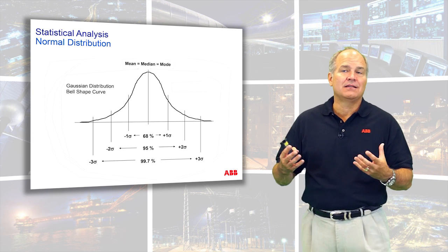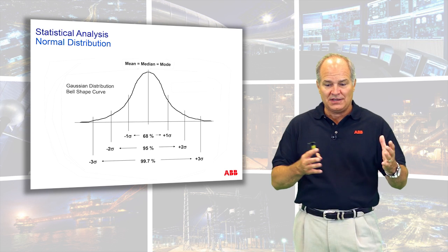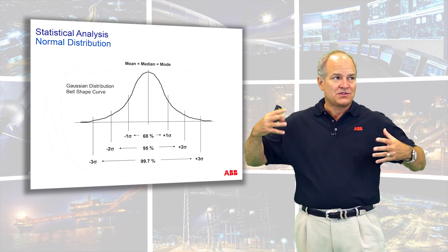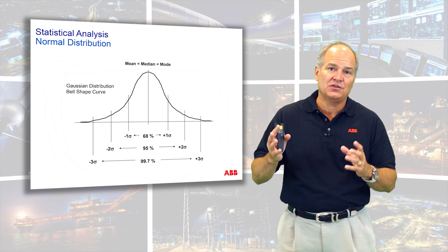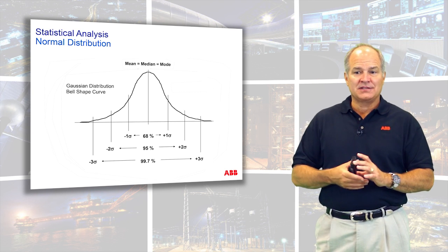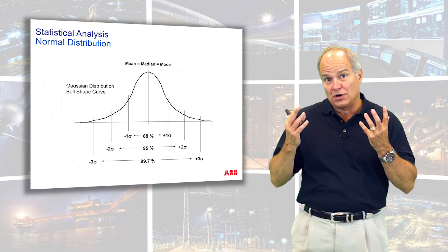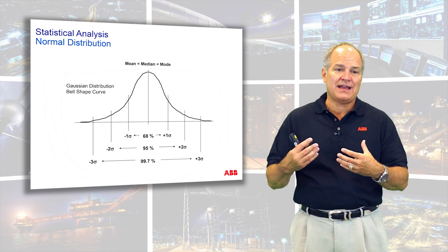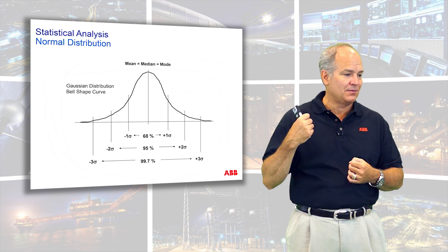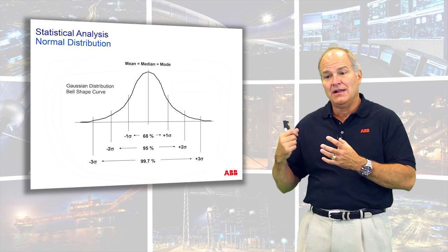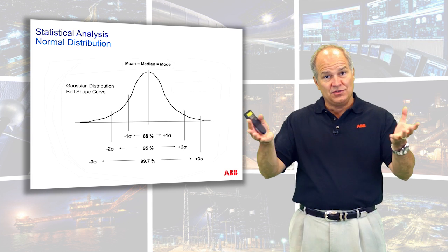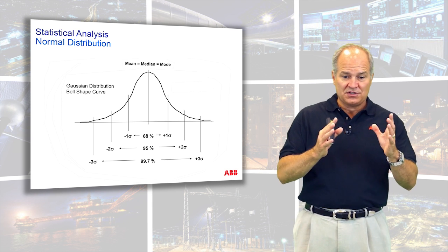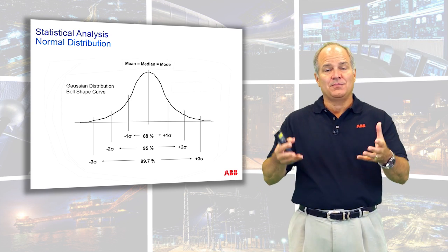And there are nice attributes of a normal distribution. It's predictable. You kind of know where it's going to be. And a signal just sort of floating around is going to have very close to normal characteristics. So if we can measure the normalcy of a signal, we can tell if it's working. If we have an actuator at a limit, or a control that's oscillating, or nonlinear attributes being introduced to the process, you no longer have a normal curve. And so it starts to shift to one side or the other, and that opens up where we're going next.